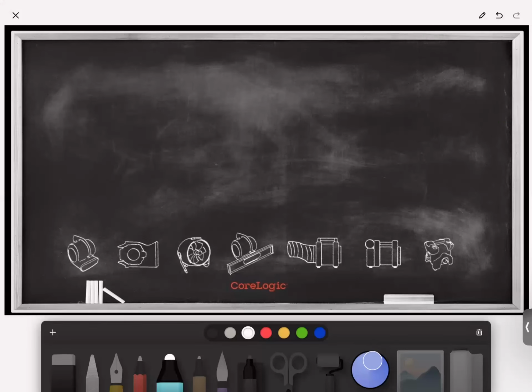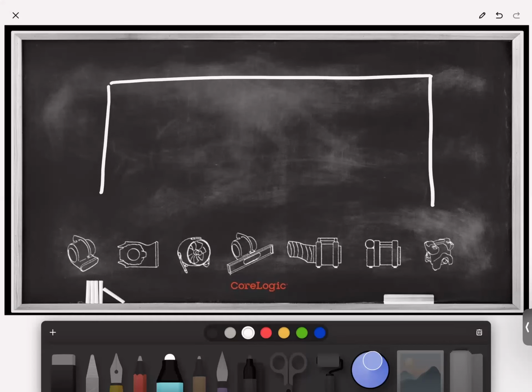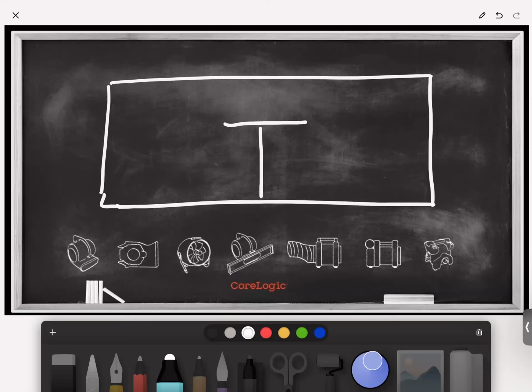And if you really want to be accurate, I won't stop there. I'll draw a really simple floor plan. And with yellow here, I'm going to indicate some of the places where you might want to take a temperature and humidity reading, right? First of all, a temperature and humidity at this location would be really valuable if I compared it to a temperature and humidity at this location. If this is a drying chamber, and I have a dehumidifier installed somewhere in this chamber, wherever that dehumidifier is, we'll say he's right here. By taking a measurement in these two different locations, I can verify that the circulation is occurring fully between these two locations if they match.